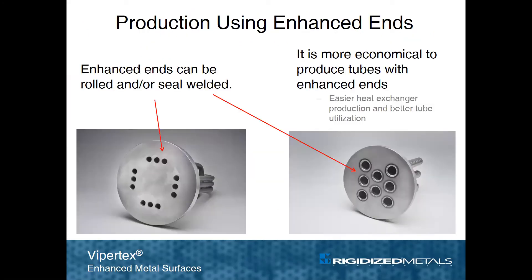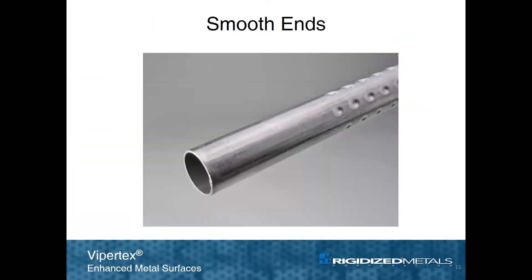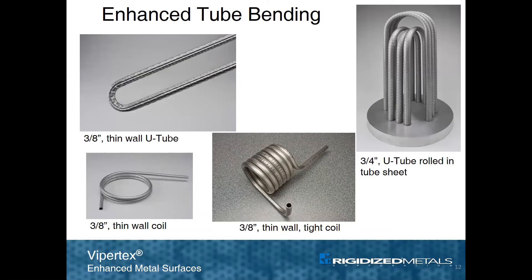Vipertex enhanced tubes are readily expanded into tube sheets using a roller die procedure, and a demonstration video can be viewed on our website. Tube sheet junctions can also be seal welded if necessary. While it is more cost effective to work with a tube that is textured all the way to the end, it is also possible to specify smooth ends. Vipertex tubes are readily formed into coils and U-bends as needed for certain heat exchanger designs.